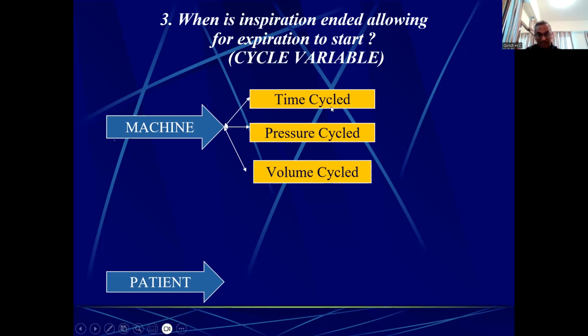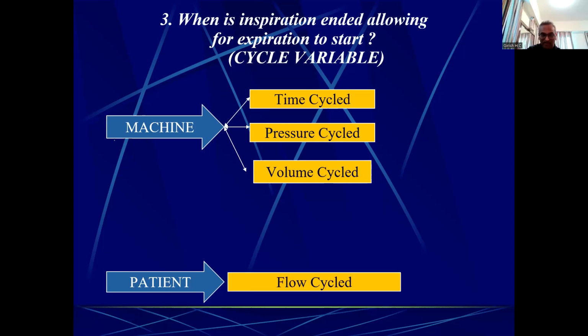Time cycling is what we clinicians tell the machine to do. Now I am asking, how can the patient tell the machine, I am ready for exhalation, please open the exhalation valve? Medulla oblongata. No, that is not available yet. Critical flow, sir. Minimal critical flow rate. So that is called flow cycling. Let me explain the concept, then you'll understand. That is called flow cycling.